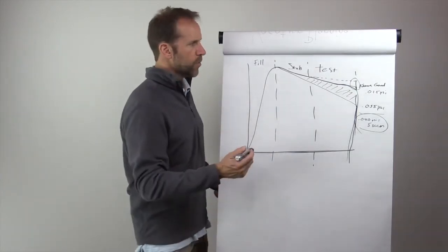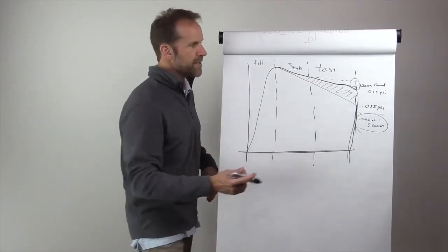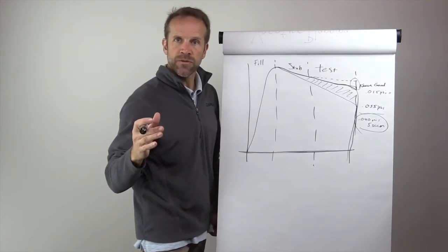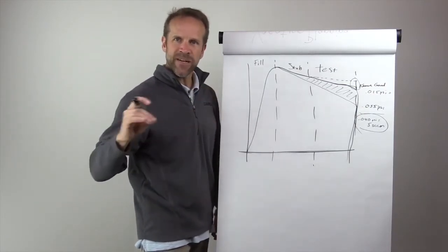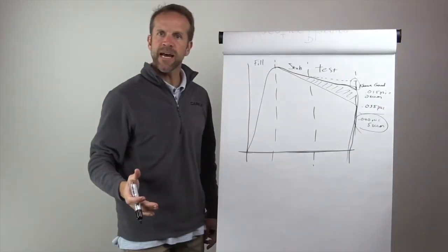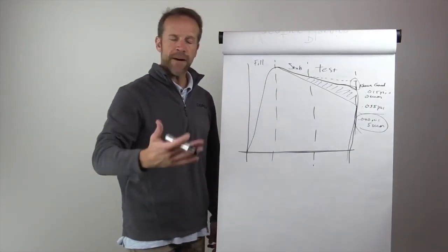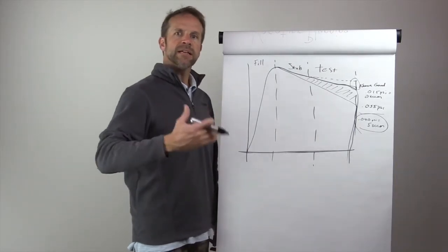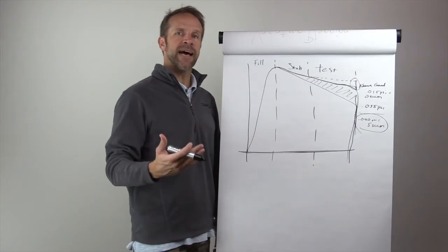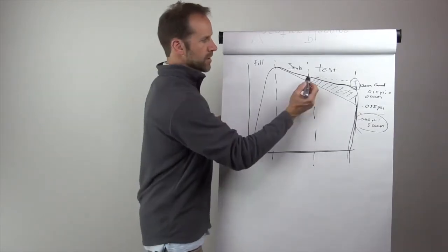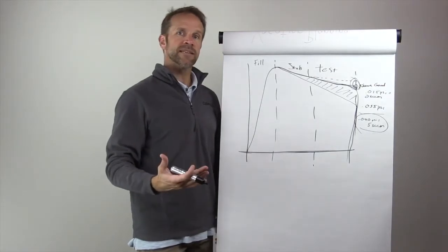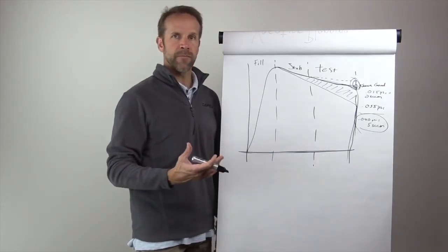When you get a negative leak, what is happening is you're not necessarily gaining pressure. To the instrument, this 0.015 psi equals 0 SCCM, because it essentially tares out the pressure loss of a known good part. So 0.015 psi equals 0 SCCM. When we run a test and we lose, say, 0.01 psi, the instrument can only display that as a negative flow rate. It lost less pressure than the part that we calibrated to, so the only way the instrument can display that is as a negative number. So just keep that in mind.